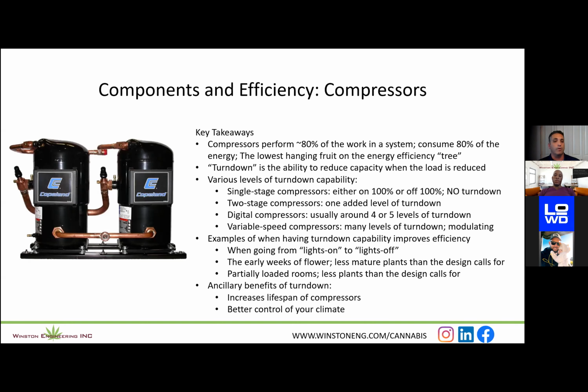So how do we get more efficient with that? We're really looking for turn down capability. There are various levels of turn down in terms of compressor designs. Let's start with no turn down, which is a single stage compressor, probably representative of 90% of residential units on the market right now. That means the compressor is either off or it's 100% on. There is no in between.